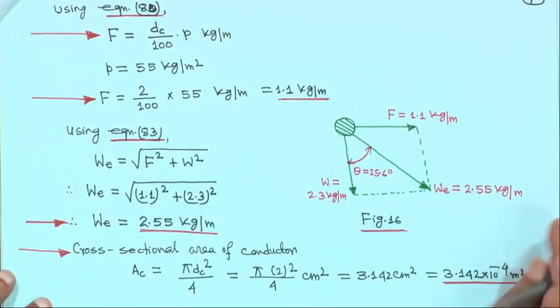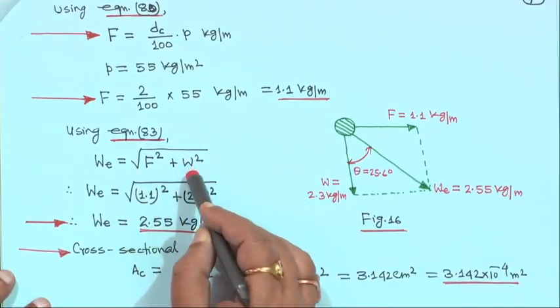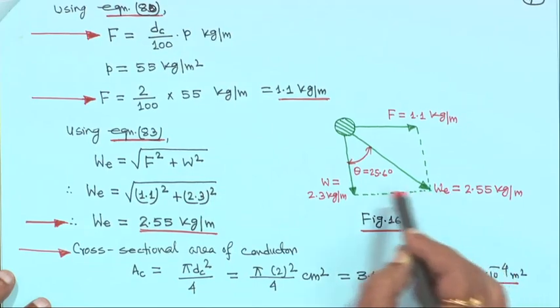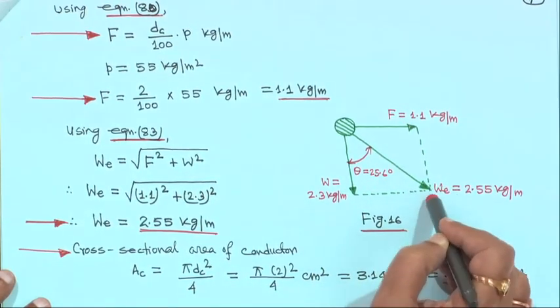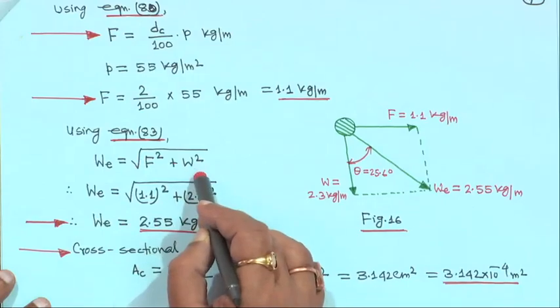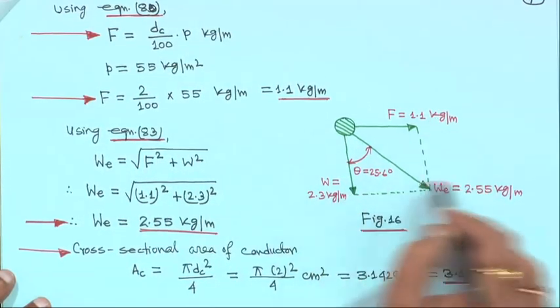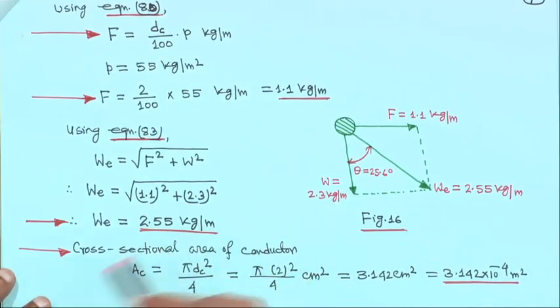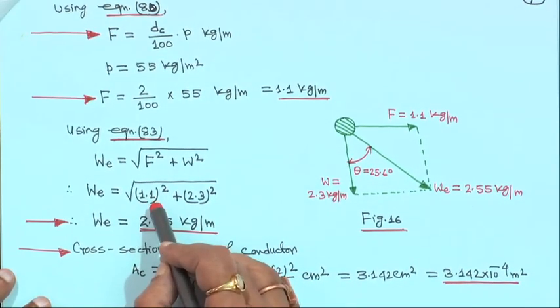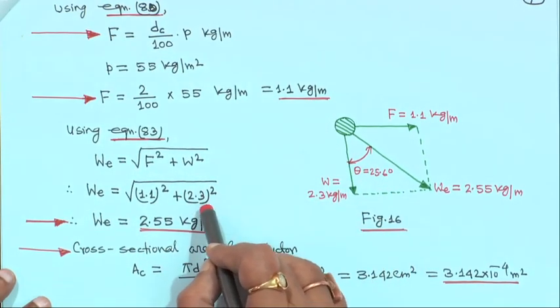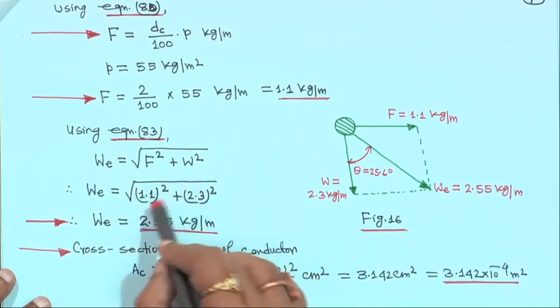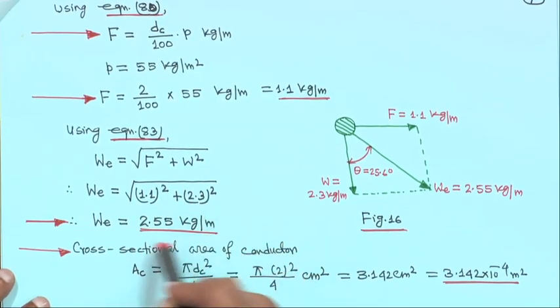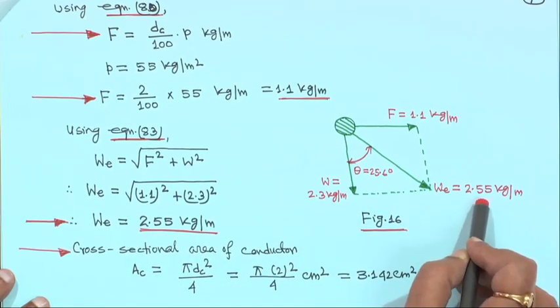Using equation 83: We is equal to root over (F squared plus W squared). F is 1.1 kg per meter and W is 2.3 kg per meter. So We will be root over (1.1 squared plus 2.3 squared), which becomes 2.55 kg per meter. That is the resultant effective weight of the conductor.